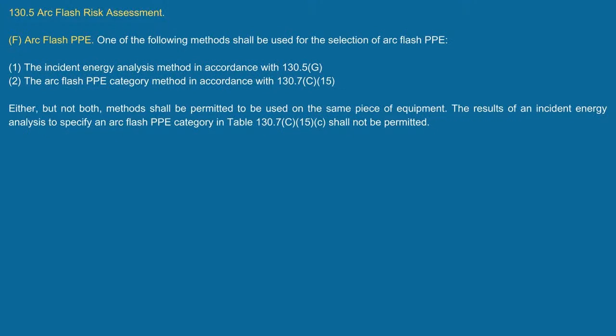Nice. Now, look at this. Arc flash PPE, it says one of the following methods shall be used in selection of PPE. Now, you have the incident energy analysis method. We're going to look at this next week, that's table 130.5G. That is where I'm doing the calculation per Annex D. And the second method is the category method. That is where? In tables 130.7, C15, A and B. And that's where you're working on it. And C is where you select the PPE.